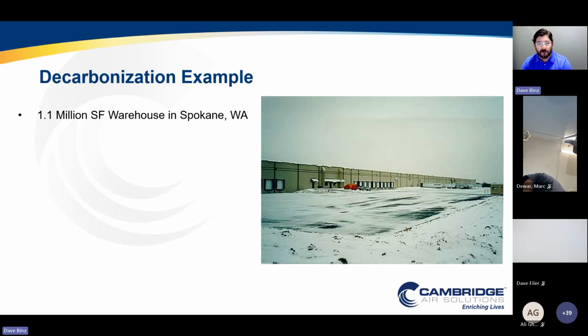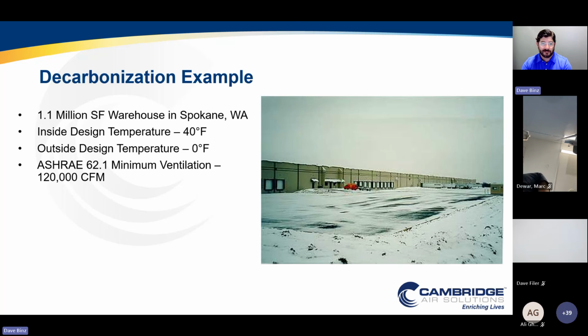So this is actually a 1 million square foot warehouse located in the state of Washington, Spokane. They were really providing minimal heat. It was just a large distribution center, roughly only 40 degrees inside the space, so not a very high indoor heating load. It got close to 0 degrees outdoors. To meet your indoor air requirements, it only needed 120,000 CFM of mechanical ventilation. So over 1 million square feet, that's a fairly small amount of outside air. And the total heat load was around 12 million BTUs, or 3.5 thousand kW.